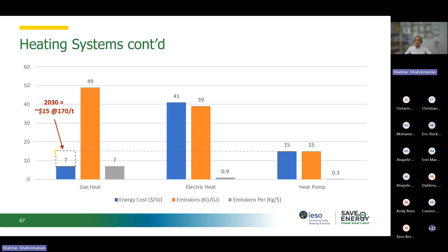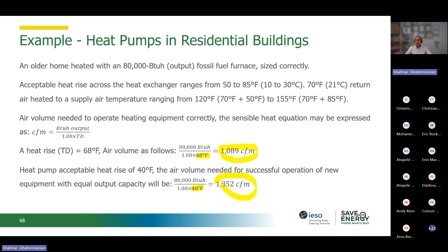I have an example here regarding the temperature difference in a residential building. If we run a combustion system, we require a higher temperature difference, so at the end of the day we require a lesser amount of airflow coming to our building. But with a heat pump, because of its capacity and the temperature rise or variance, we require almost double the CFM of air. So you need to be careful when the contractor comes — they need to look at that and do the calculations for you as well.